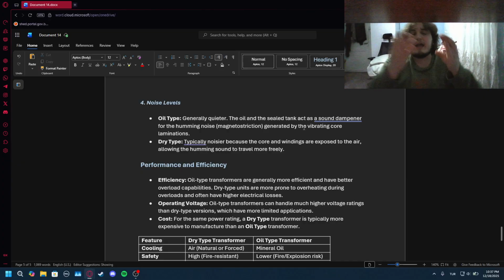Obviously, we use oil, and we use that oil because we thought it was gonna make it so that there's no voltage problems, that they are not going to have the higher voltage jumps across this stuff. And when you use, let's say, a circuit breaker, it's not going to cause a problem in the transformer and such and whatnot. This is why we use oil. And dry type is basically, it's cheap. Sorry, it's not cheap. It's expensive, but it's safe. It's really safe. We don't want people to die. This is it. For the same rating, a dry type transformer is typically more expensive to manufacture than an oil type.